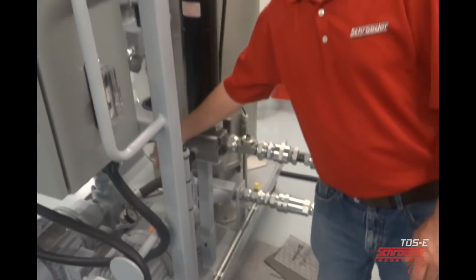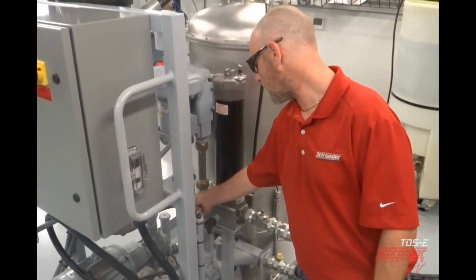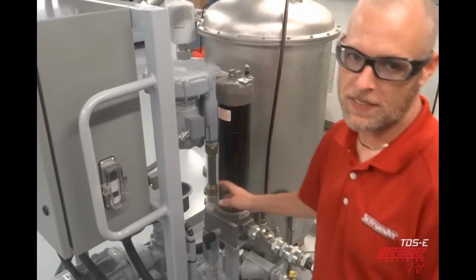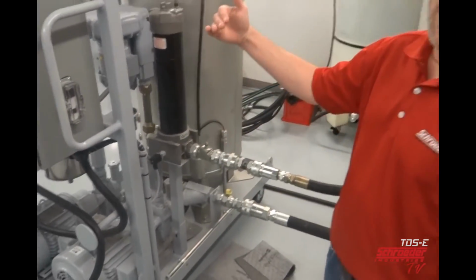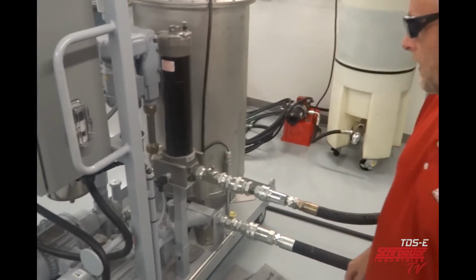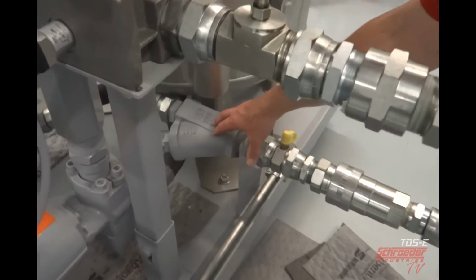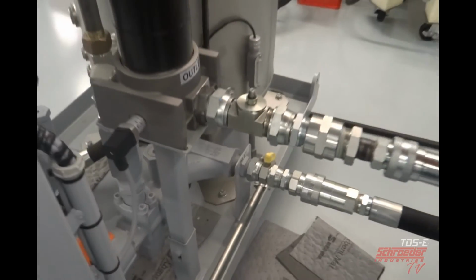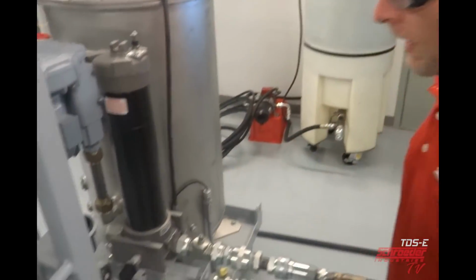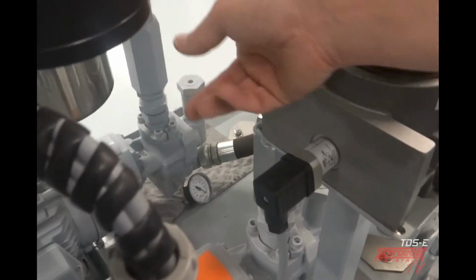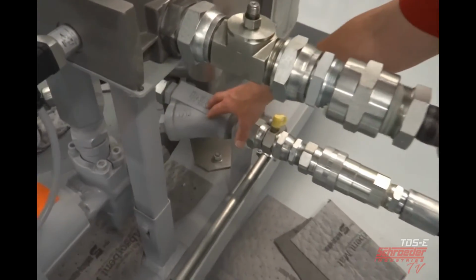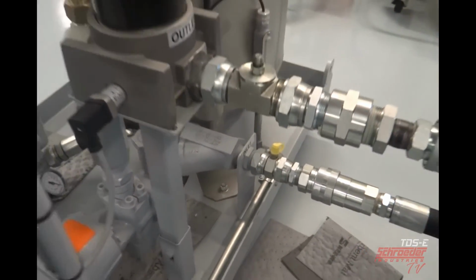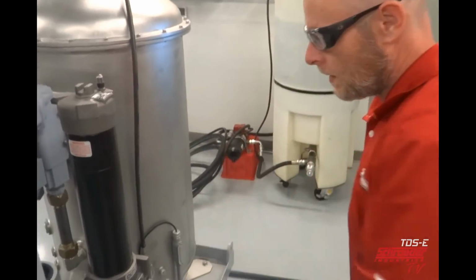A vacuum gauge is also included so the user will be aware of any restriction on the suction line. If there is a restriction, the gauge will peg up. If there's heavy contamination, you may also have to clean the suction strainer. The way you can tell this is by the vacuum gauge. If the vacuum gauge pegs up, you'll know you have a restriction on that line. Check for any and all blockages in the suction line from the reservoir tank.